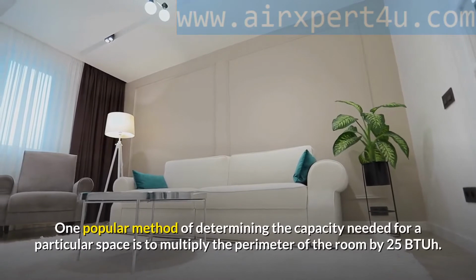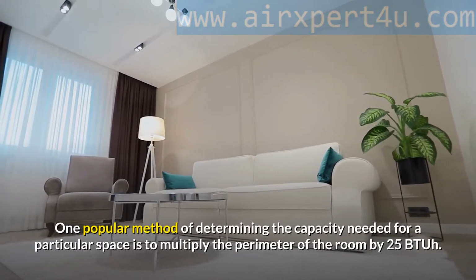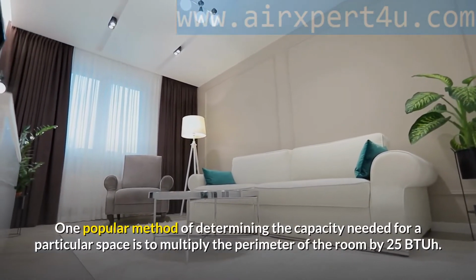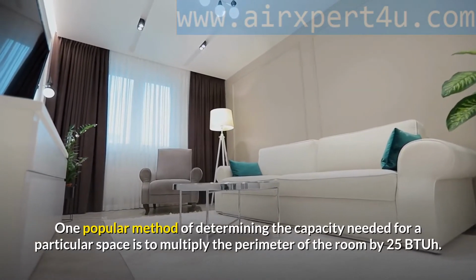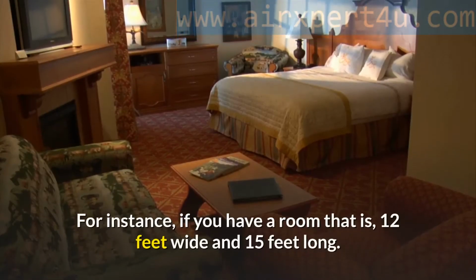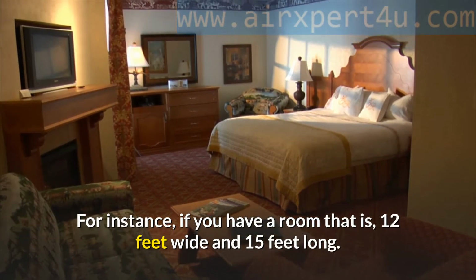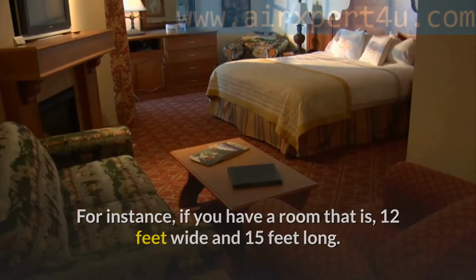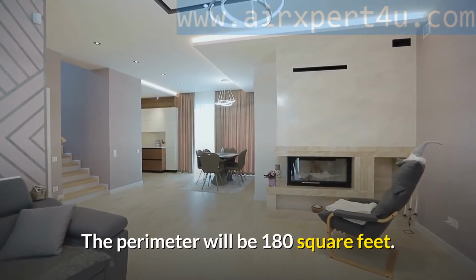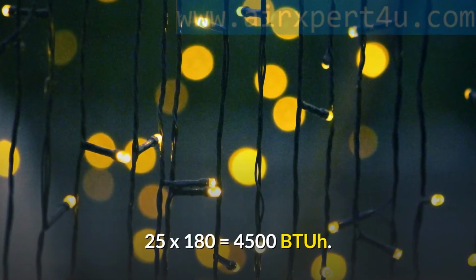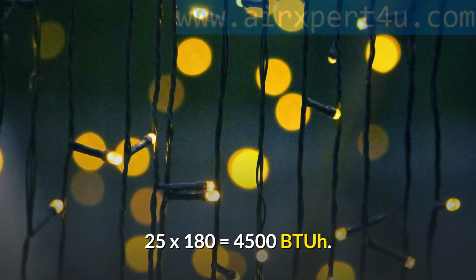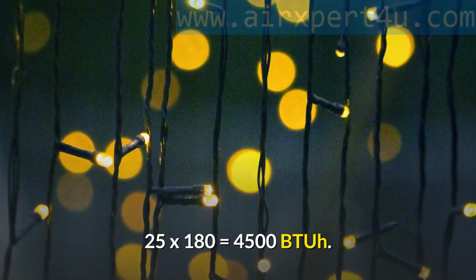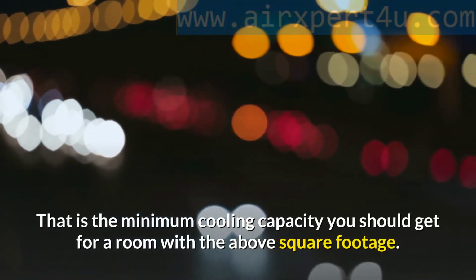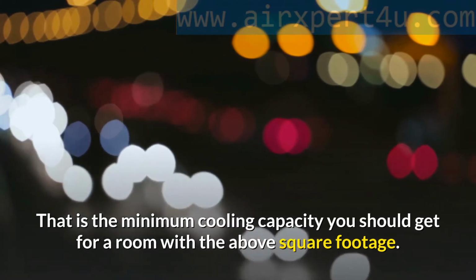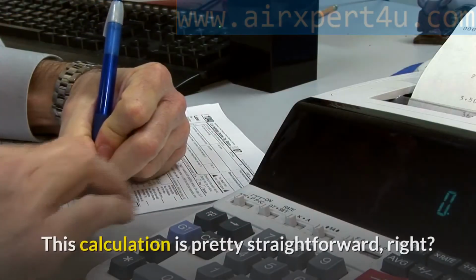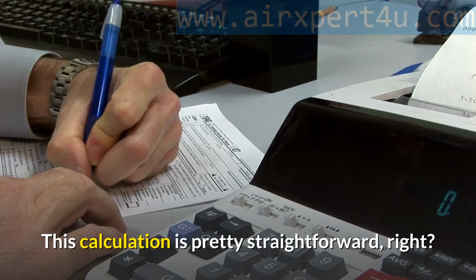One popular method of determining the capacity needed for a particular space is to multiply the area of the room by 25 BTUH. For instance, if you have a room that is 12 feet wide and 15 feet long, the area will be 180 square feet. 25 times 180 equals 4,500 BTUH. That is the minimum cooling capacity you should get for a room with the above square footage. This calculation is pretty straightforward, right?